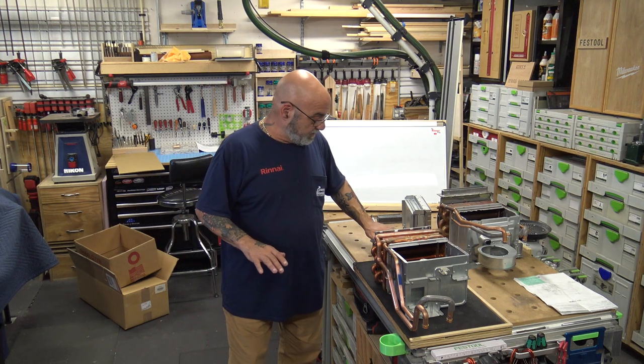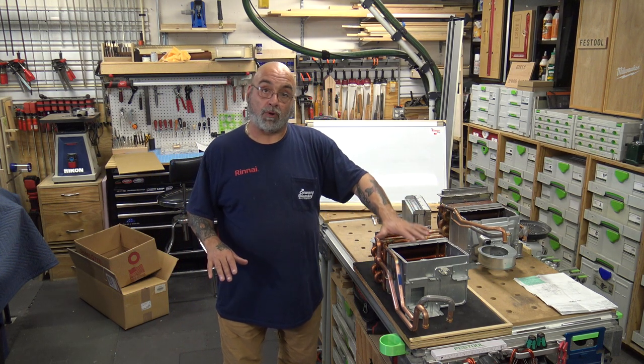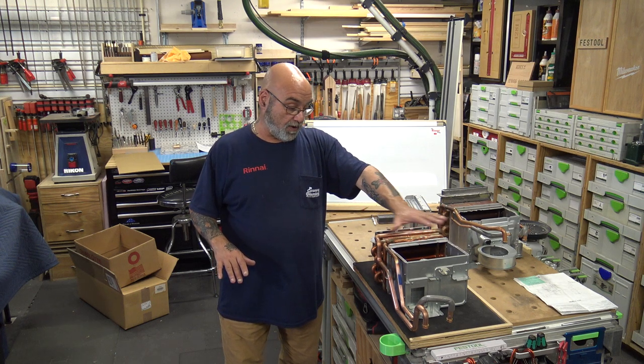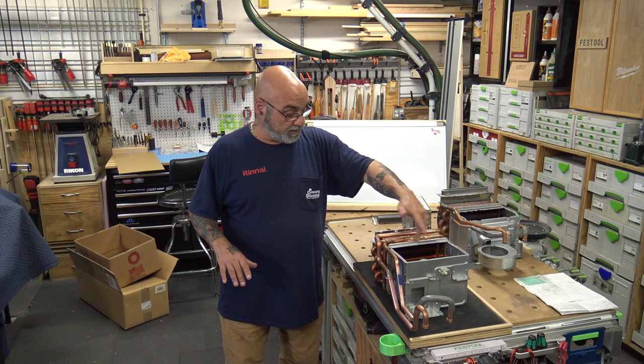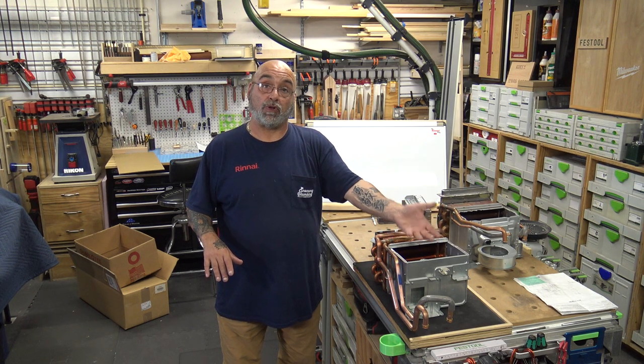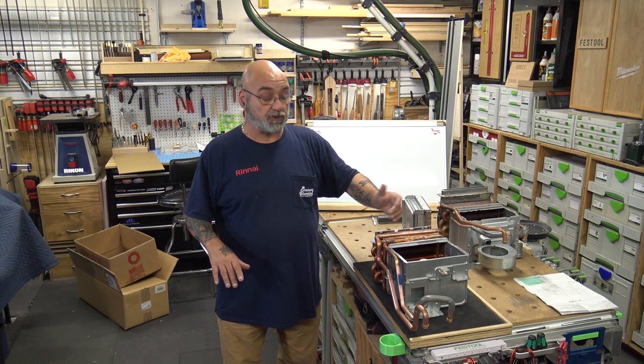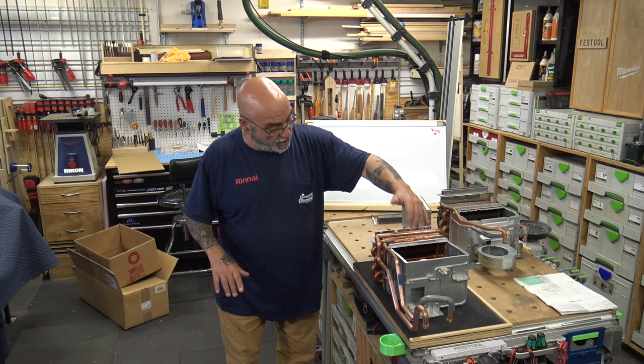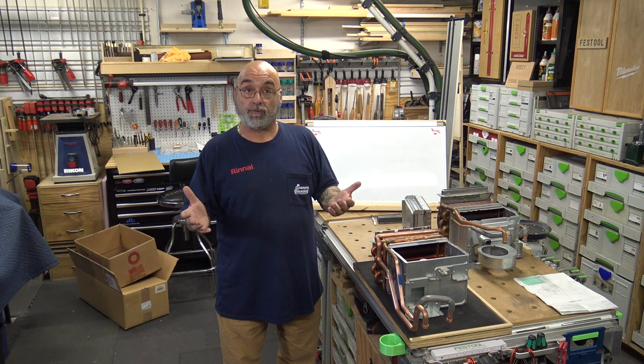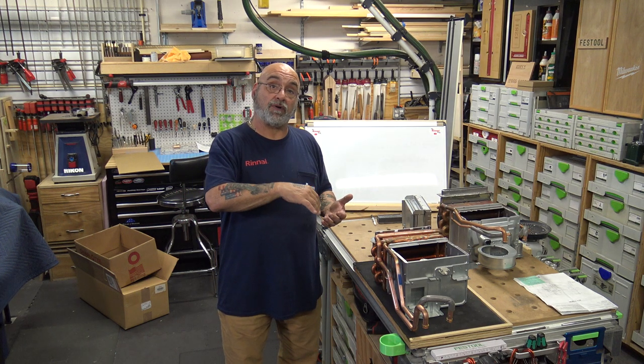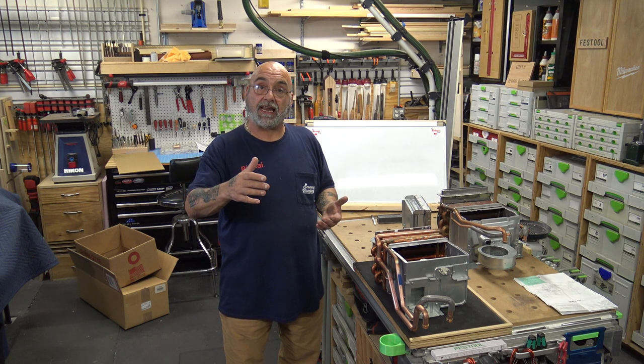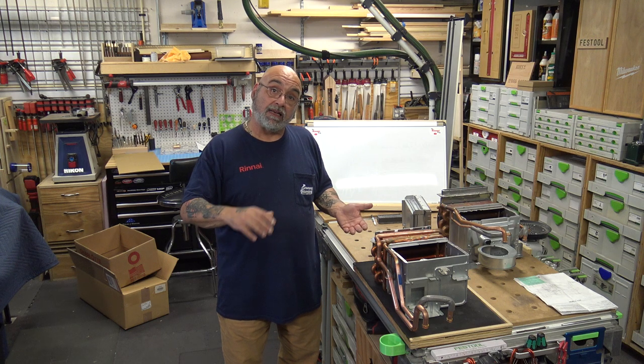And once you check the fan, then pull the burner, pull the plate, pull off the gas valve plate, pull off the top plate, and pull your burner and start doing your inspection. Use your flashlight, look up, you can see, and then go through the process of cleaning the burner, blowing it out, vacuuming it out, just dropping it a little bit to loosen debris.